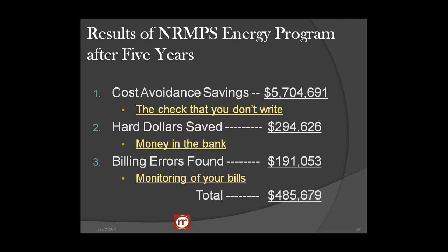Now, you need to understand as well that the power company's not the bad guy here. We're a customer with 29 schools. We have some 175 accounts with somewhere over 300 meters, and we're just one customer. How many meters will a power company read during a month? So the odds are that something might get entered incorrectly or a meter might fail, and it's up to the customer to monitor bills and to work with the power company. I think that's extremely important, and this shows almost $200,000 in savings just by monitoring it. And don't dump it on the secretary that pays the bill, because she does a great job at paying the bills, but she does not understand how to read that bill.